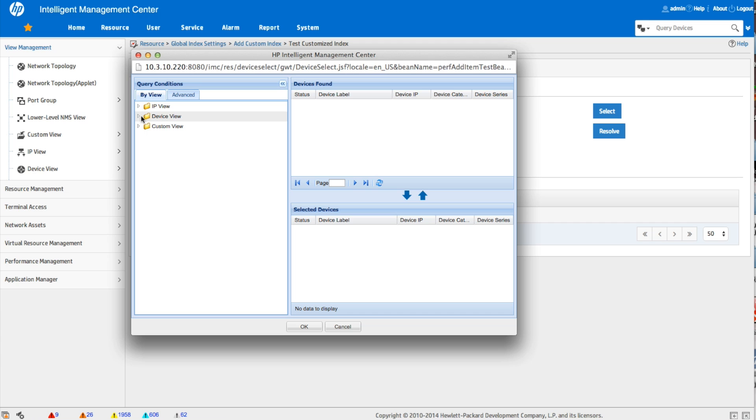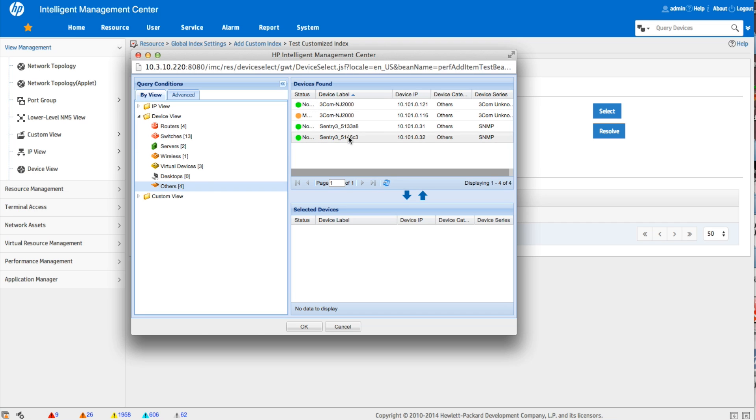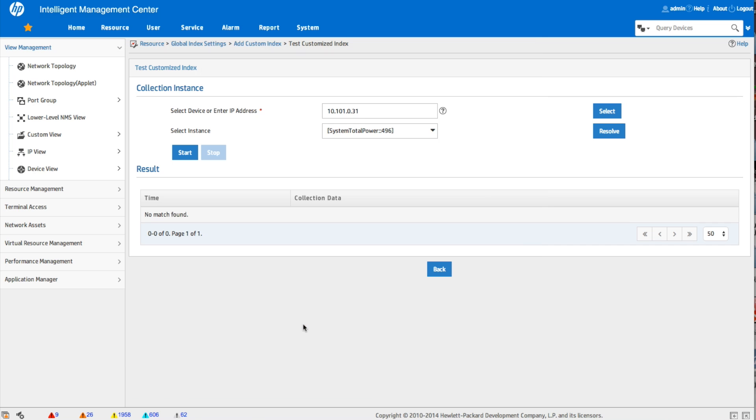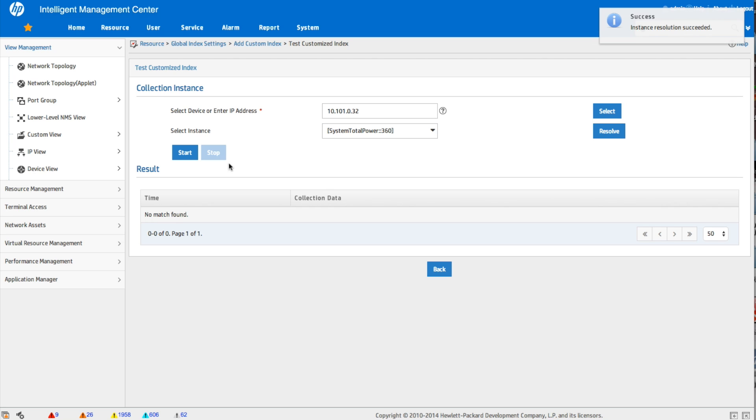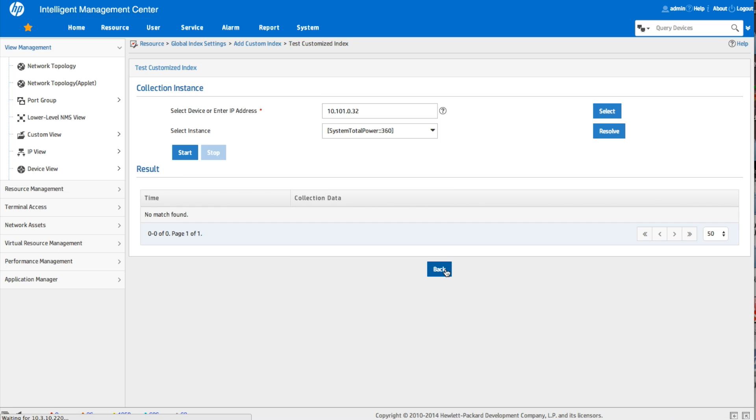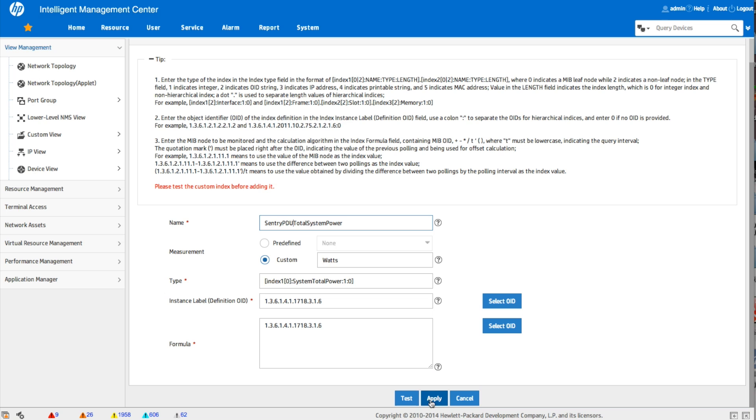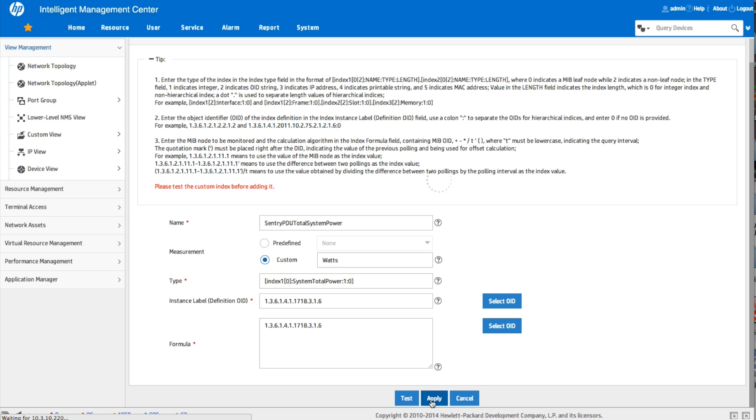So what's nice about this is once you've defined this once, I'm going to be able to go in and apply this to the other one. So if you have a custom index for whatever kind of device you have, whether that's UPSs, things like that, you can basically do it one time for that entire range of devices and you should be good to go. So to be a little more descriptive here, I want to use PDU, we'll go apply. There we go. It's been done successfully.